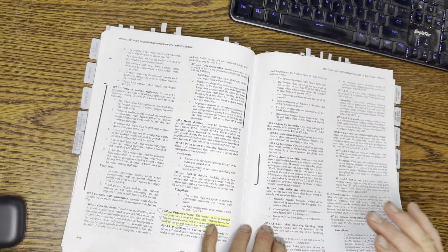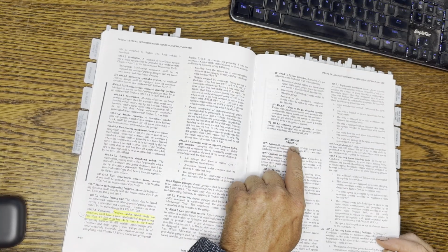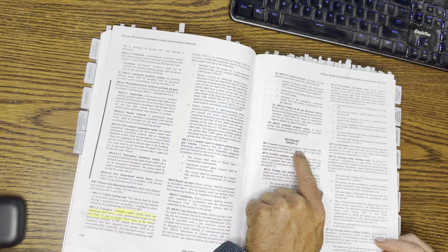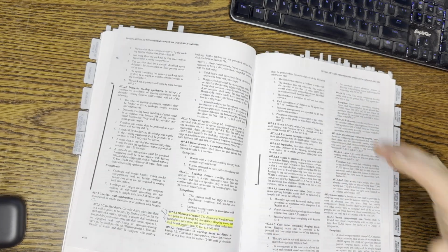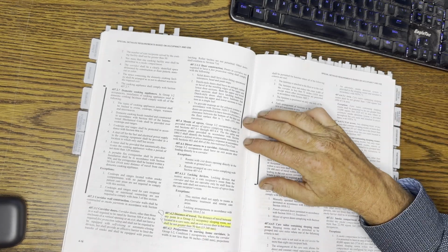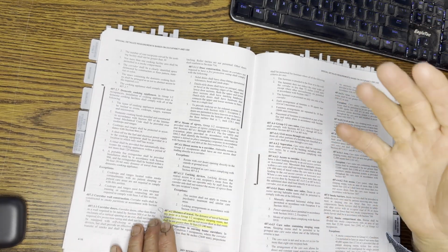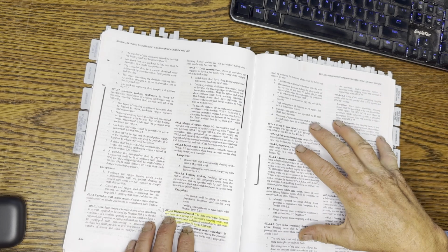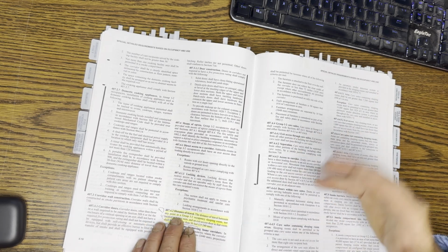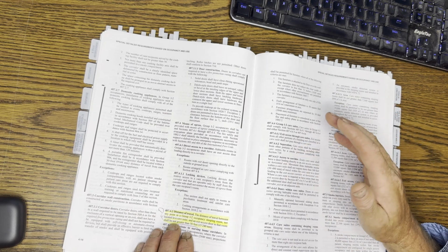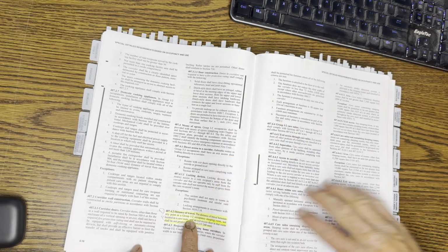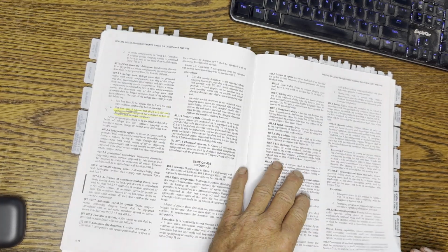Oh yeah, let's just talk really quick. So when you're in Chapter 10, we'll get there, but just be aware. So 407, if you look, is a group I2. I2 is a hospital, okay? So keep that in mind. Hospital, right there. You'll be asked a question about, let's say, distance of travel. I mean, their classic example right there. Exit access travel distance or whatever it might be. So you go to Chapter 10, look at the means of egress section for total exit access travel distance or common path of travel. But because they say I2, you got to go to Chapter 4, because Chapter 4, Section 407, has all sorts of stuff in I2.